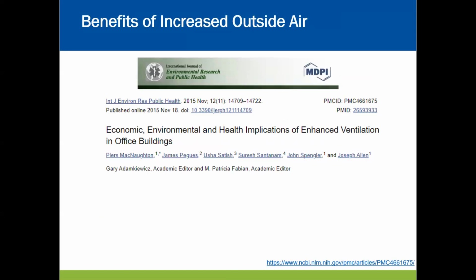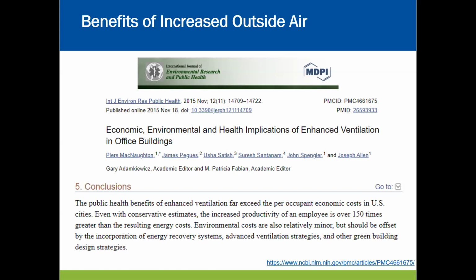And lastly, benefits of outside air. There have been so many studies about the benefits of increased ventilation. Keep in mind the ASHRAE standards are a bare minimum, and it's highly recommended to go higher than those bare minimums. There are a lot of studies, and one in particular is really comprehensive, published in 2015, about the environmental health implications of increasing ventilation in office buildings. There's some great research there, and it's a good article to read. The conclusion is that the benefit of enhancing ventilation really exceeds the cost to do so.